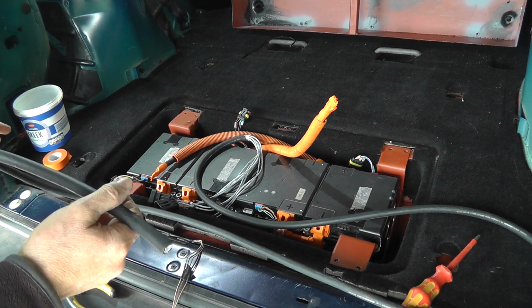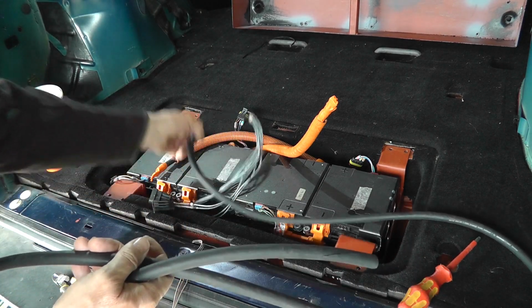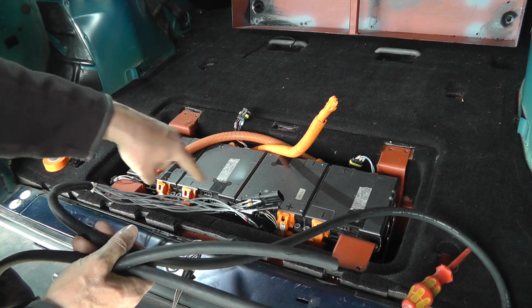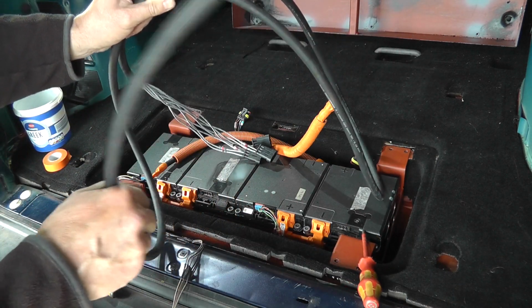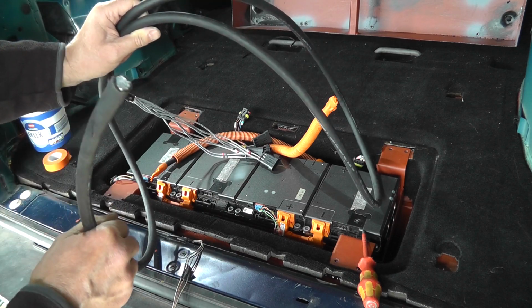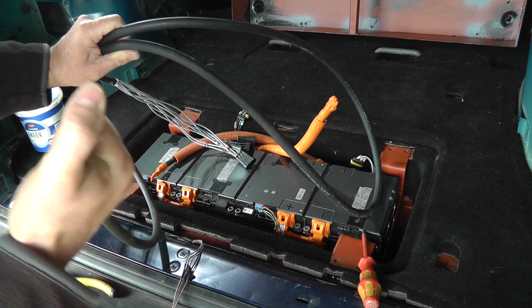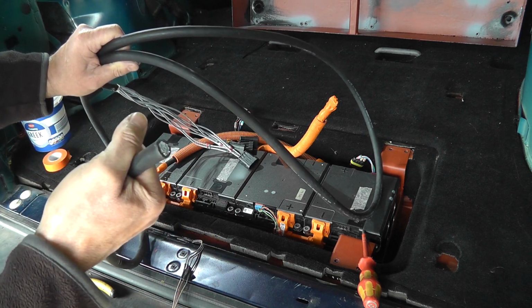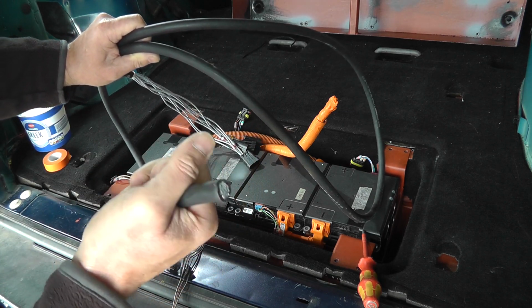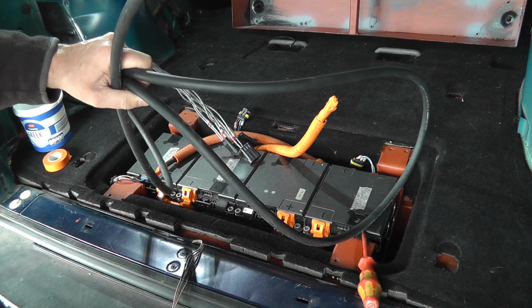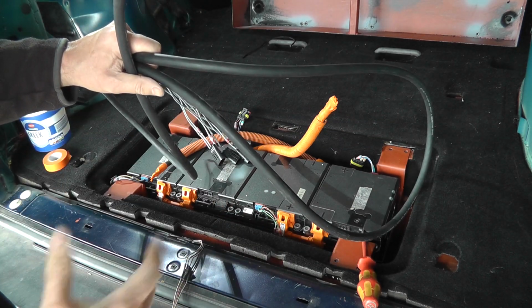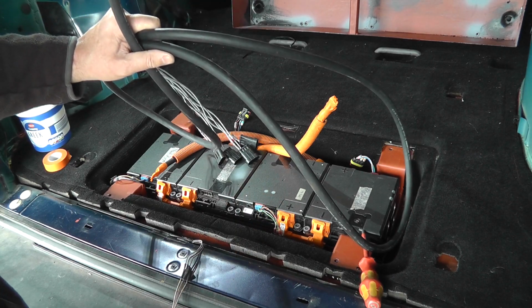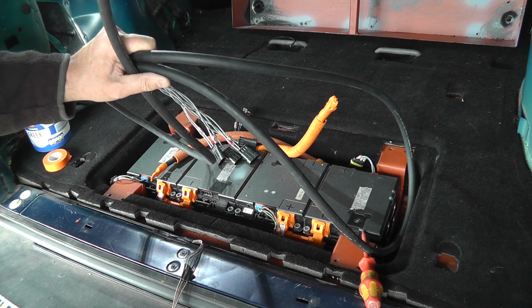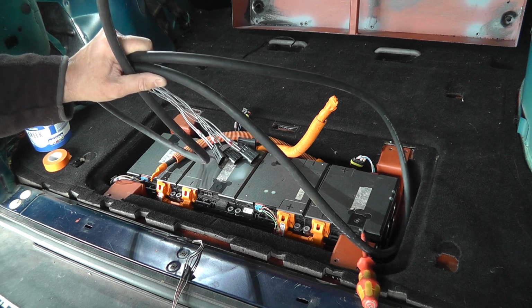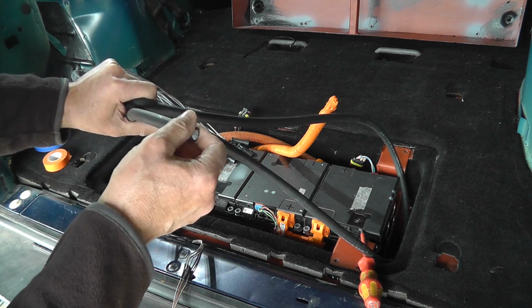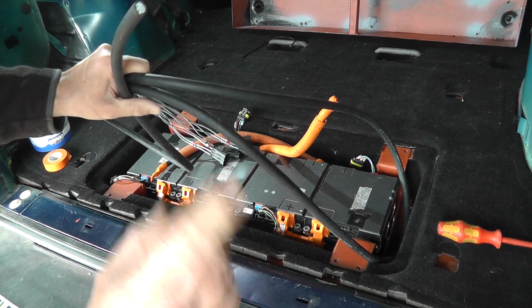I very nearly did a stupid thing there, guys. I was just about to start plugging the BMS connections into the batteries, and then cut it to length. That's a bad idea, don't ever do that. This would then have been live, and I would have been cutting into a live cable. Okay, it's only live with 60 volts, but that's still enough to blow a hole in your cutters, possibly melt your wires, and maybe blow the tracks on your PCB. Anyway, whatever, it would have been not very sensible. So don't ever cut your cable when it's connected to the batteries at the other end - that's not sensible.